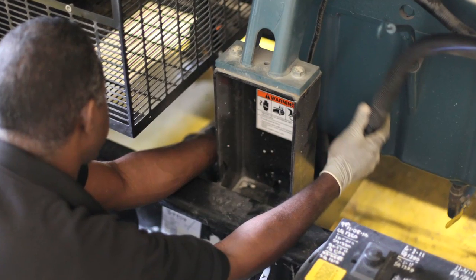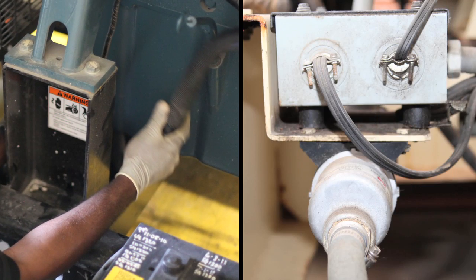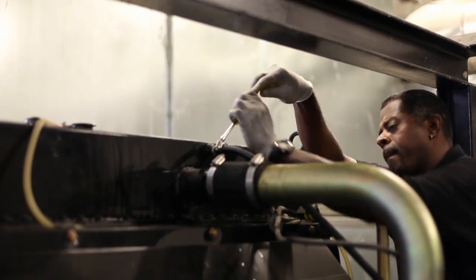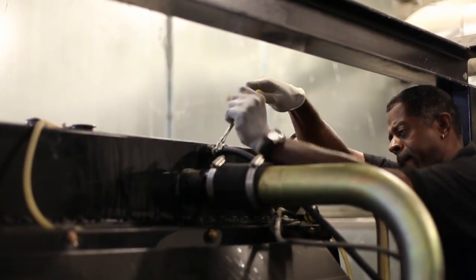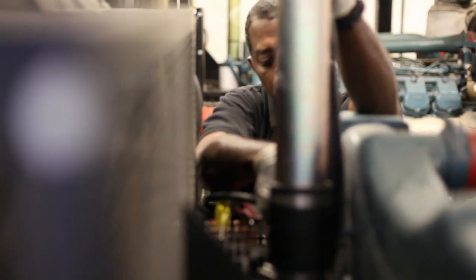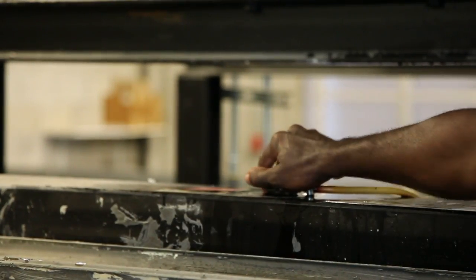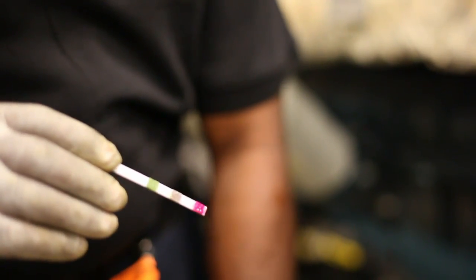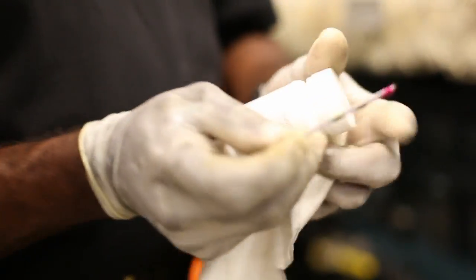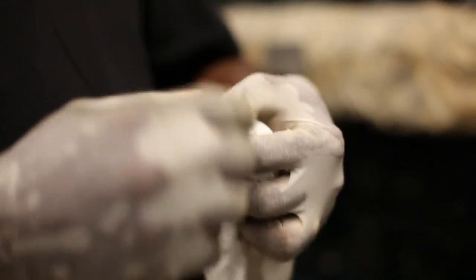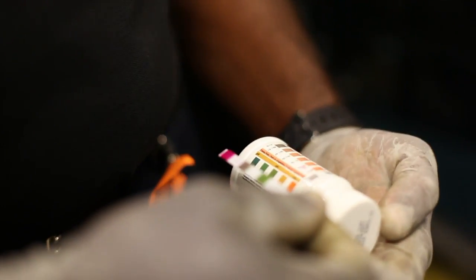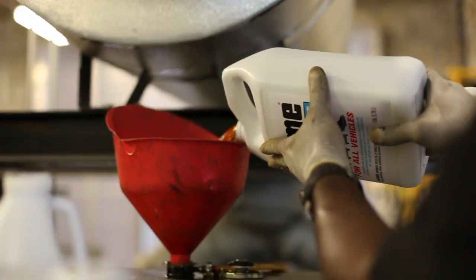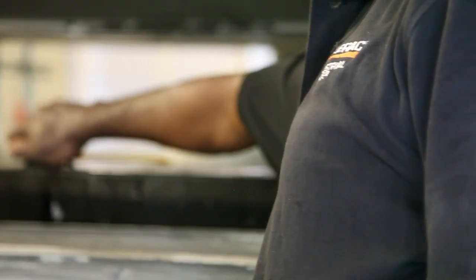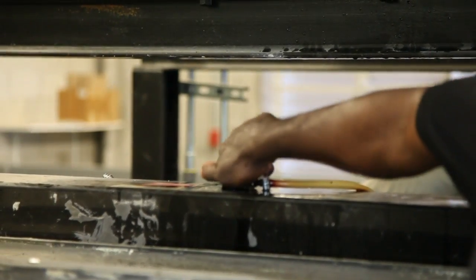We examine coolant water hoses and junction box for any sign of corrosion. We check hoses to the after coolers for tightness and leaks, bottom and top radiator hoses for tightness, remove and inspect radiator cap and coolant level. A strip is used to check the radiator coolant pH level and then used to verify coolant condition using the appropriate chart. The technician takes a coolant sample from the radiator and checks its condition. After replacing the sample, the technician adds any required coolant or changes if required. The radiator cap is replaced after examination.